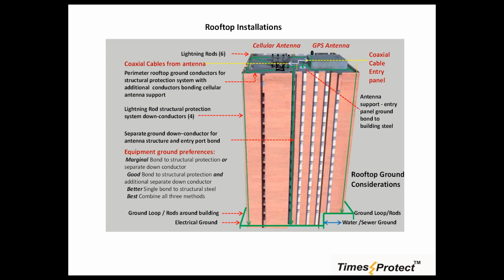If you take a look at how newer buildings are constructed with structural steel, you are going to have a knockout all over the place, because at every secondary side of the AC transformer, step down transformer, or UPS, or whatever, you have to ground the neutral, basically. So you are going to have a lot of provision in the steel buildings to make a knockout, tie all your grounding for RF, DC, AC, all the supply, all the IO ports tied to that. And that building is going to look like a huge capacitor to the lightning discharge. You're going to charge it and you're going to bleed it very, very fast.